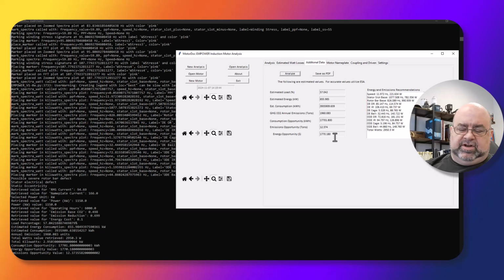For going in and taking a look at things, things I'll want to look at here: the stator slot and rotor bar related issue, this is the high frequency one. That's a lot of energy. That's not a full kilowatt. This one is really close, but that's 782 watts, and that's 991 watts. So that's basically a kilowatt related to the rotor bars.